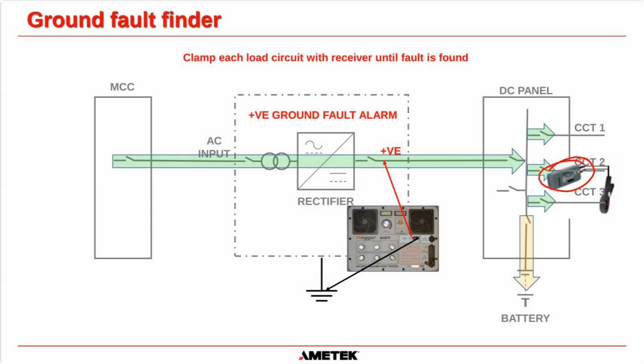And that's the important thing, why it's a low current, low voltage signal that the BGFT is sending out: if it's a very, very low moisture, soft fault, it's not enough current to evaporate that water and make the fault disappear and then make it impossible to find. So that's how you find a ground fault using a ground fault tracer. Pretty much all of them work exactly the same. It's just some of them are digital outputs, some of them are analog meters to see the signal. But they all basically inject an AC signal onto the DC system, and you can find the fault using a CT.